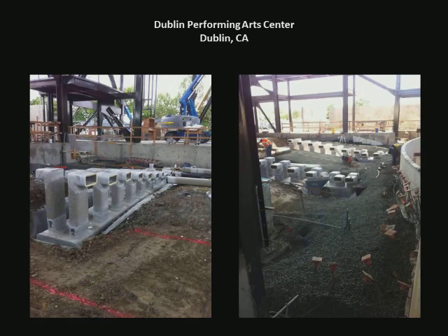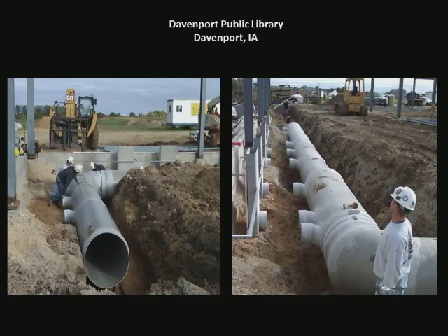Okay, let's go back to the Davenport library example again. These register boots show up as one single piece to the site. Through coordination drawings with the customer, we make sure we have the right height of boot. There's an end cap in the bottom of it, and this tap is already installed. If the job's a double wall project, let's say it's an 8-inch round tap, that's a pretty standard size for some of our boots. This tap will still be double wall so that it can match the size of this connection.